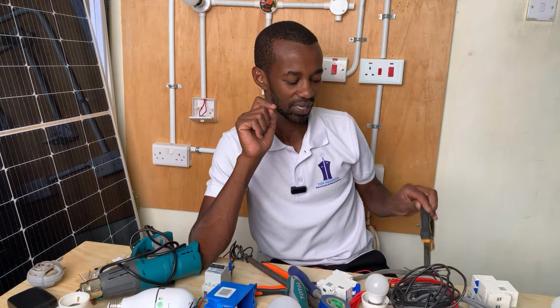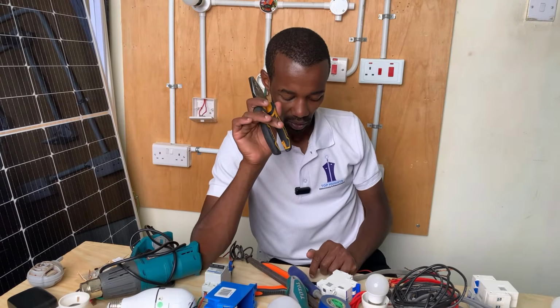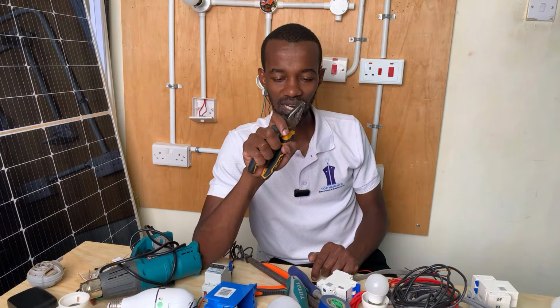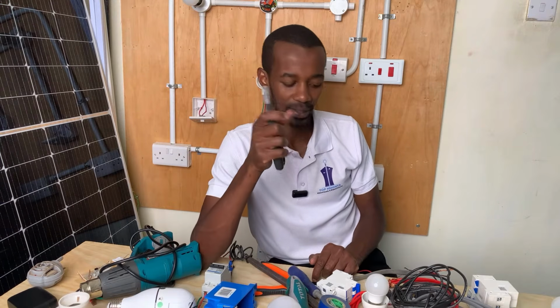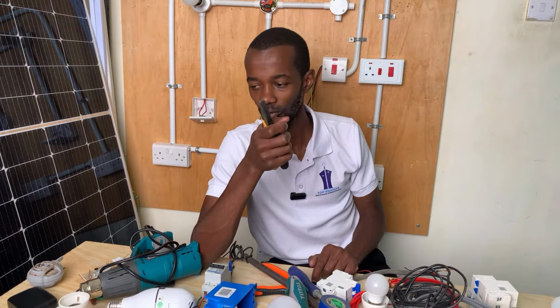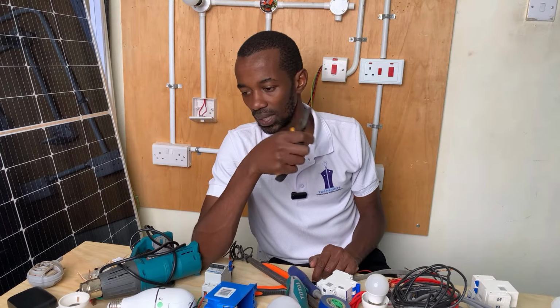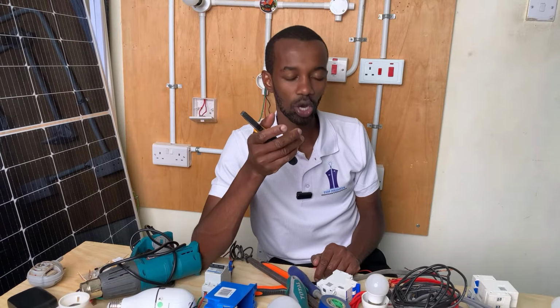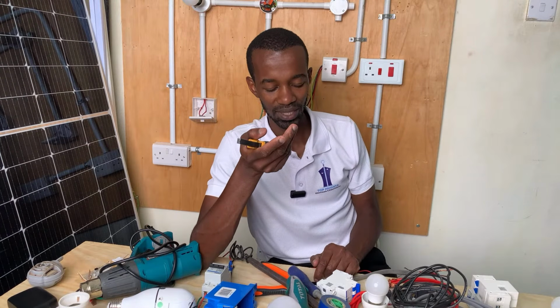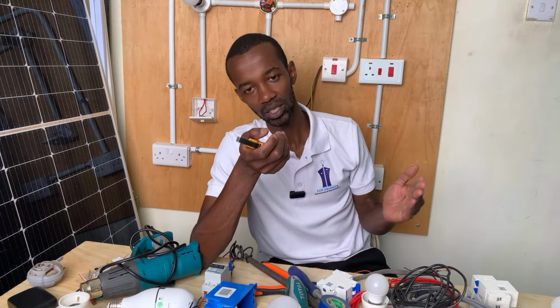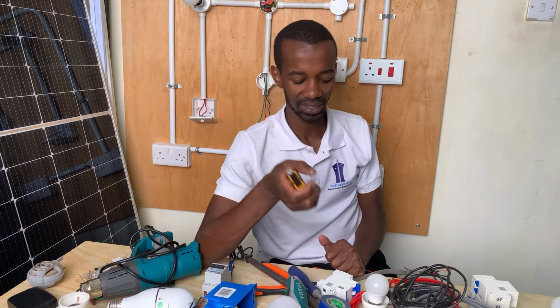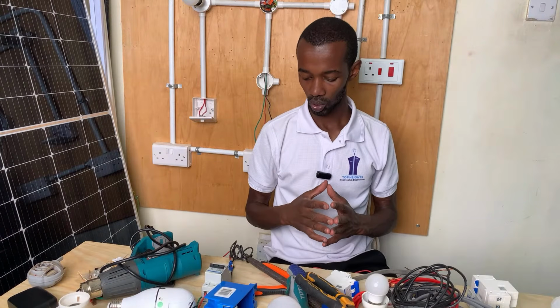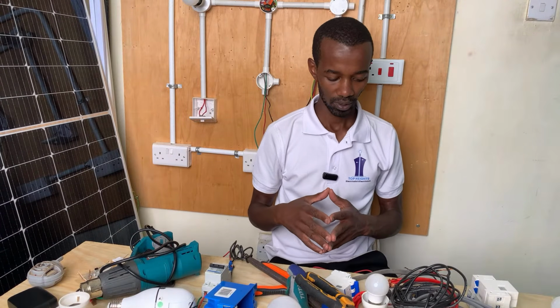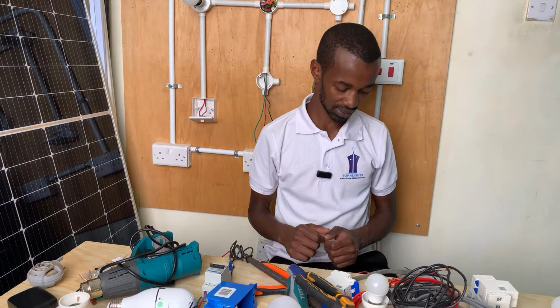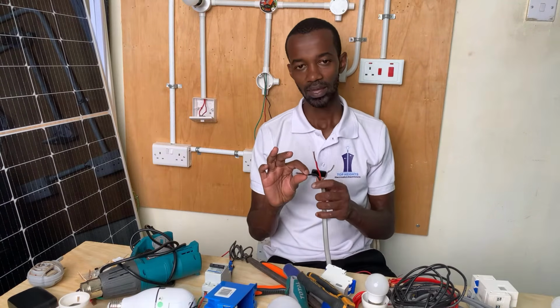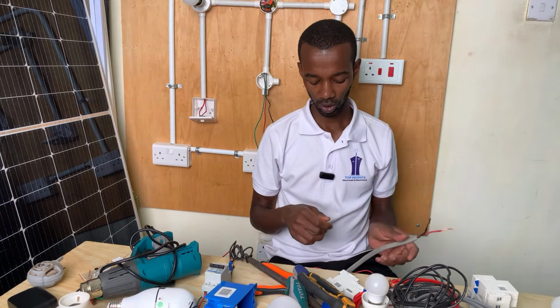The stripping tool is also very important. We've touched on how using the wrong tool while stripping insulation off a cable can reduce the number of strands or break them, reducing the effective size of that cable. That in turn brings about issues of resistance, because a reduced cable size means more resistance.